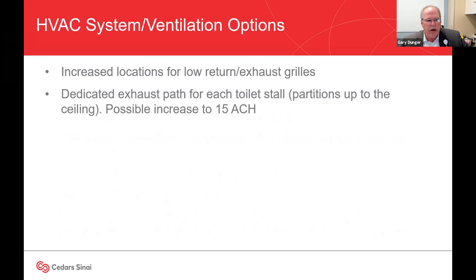Another consideration is increasing locations with low return or exhaust grills, using that laminar airflow process to force air in infectious rooms to flow downward. Also increasing air changes per hour in toilet rooms, maybe as much as 15 air changes per hour.